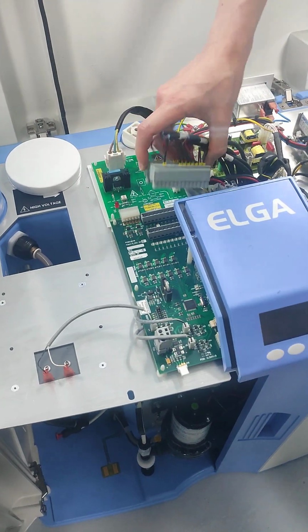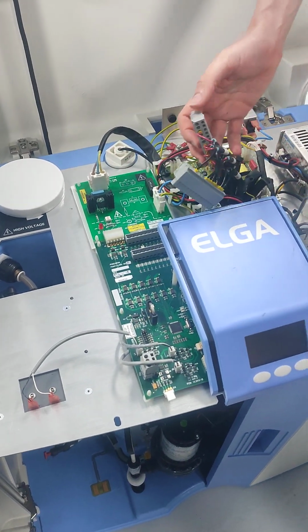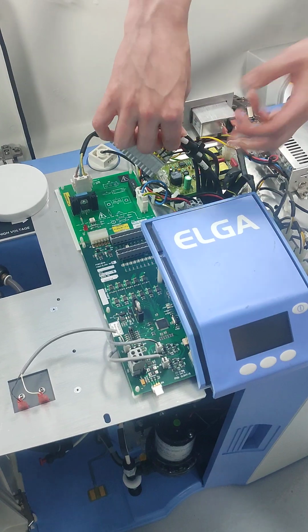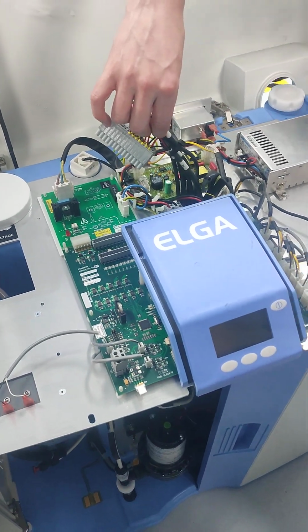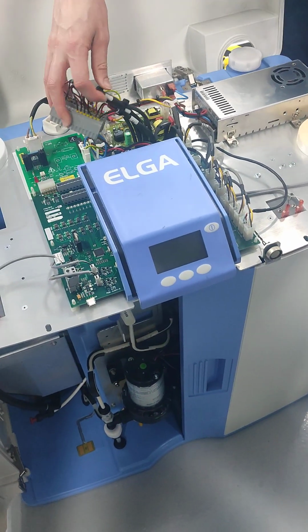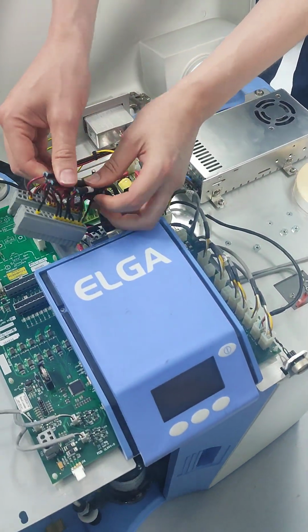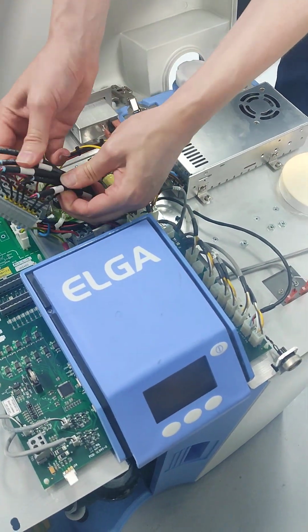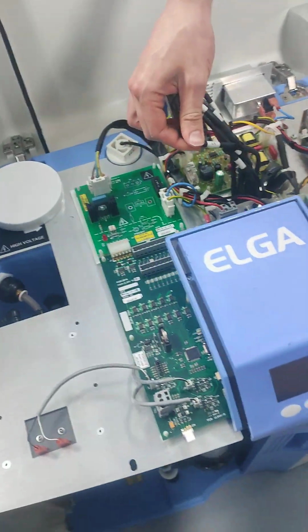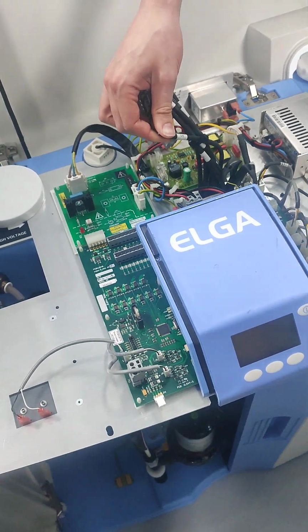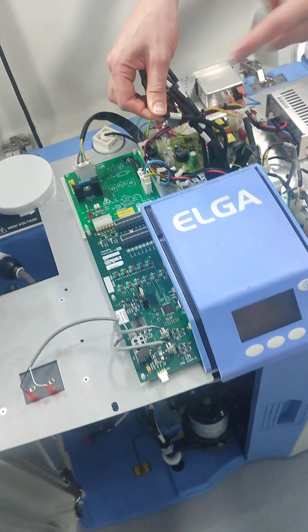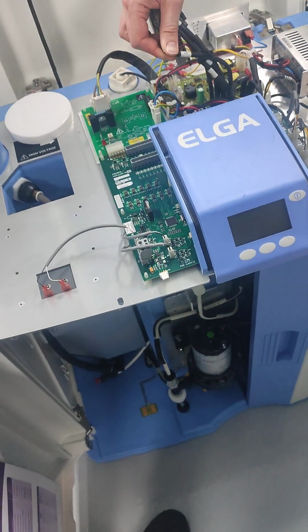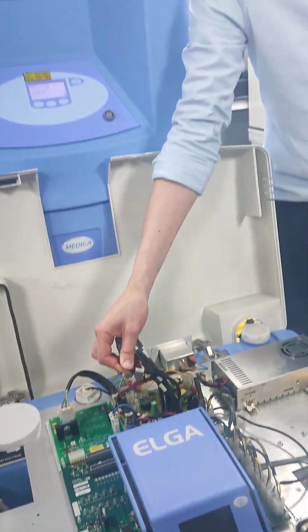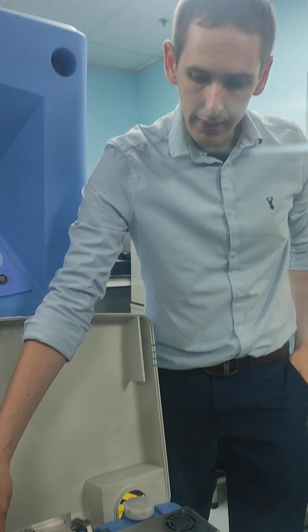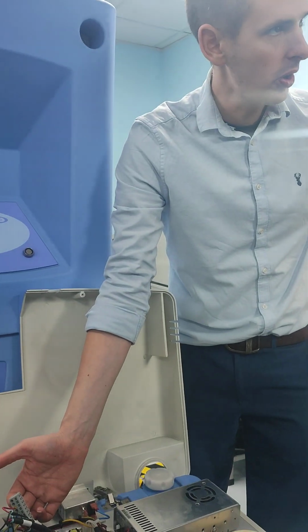All of these connections here can be removed, and they're typically for things like V1, V2, P1, P2, and we know because there's a small label which tells us what it goes off to. It's labelled here, and if we check down the bottom where that cable goes, it should be labelled down there too - so it's an easy way to tell where the wires go.